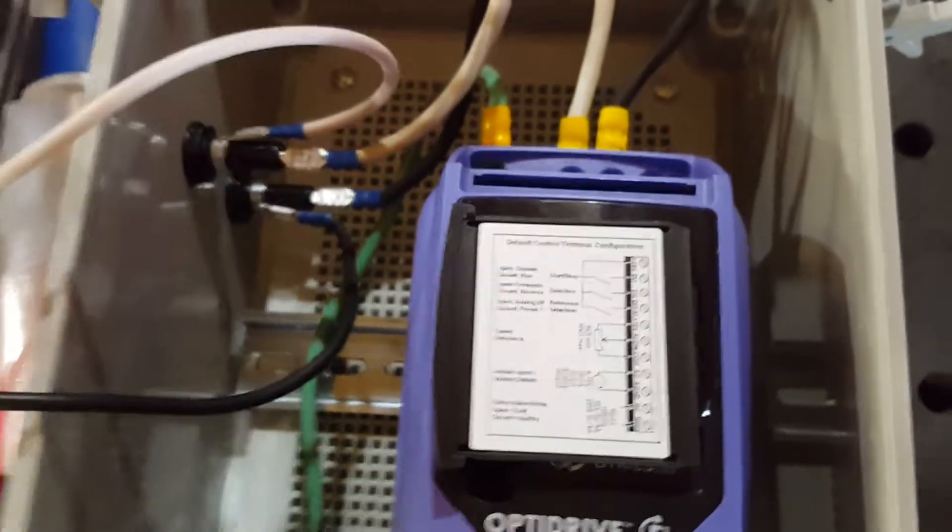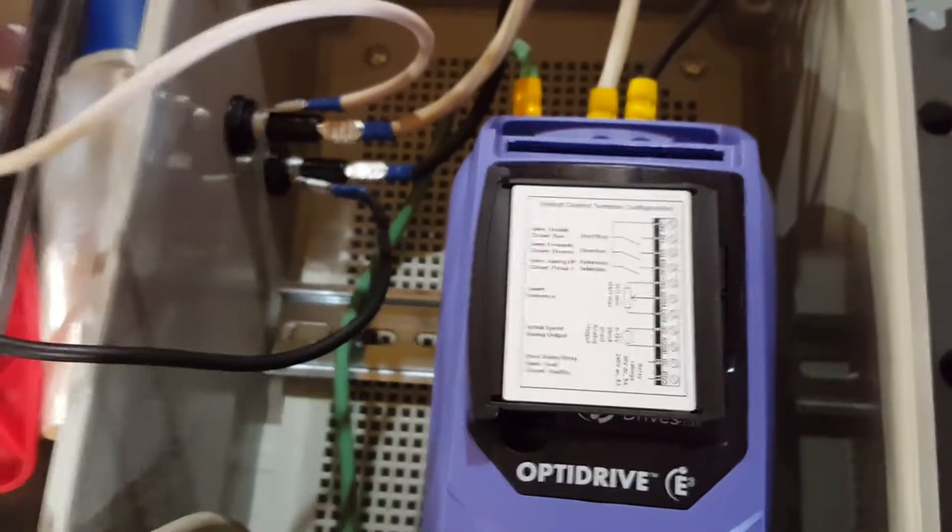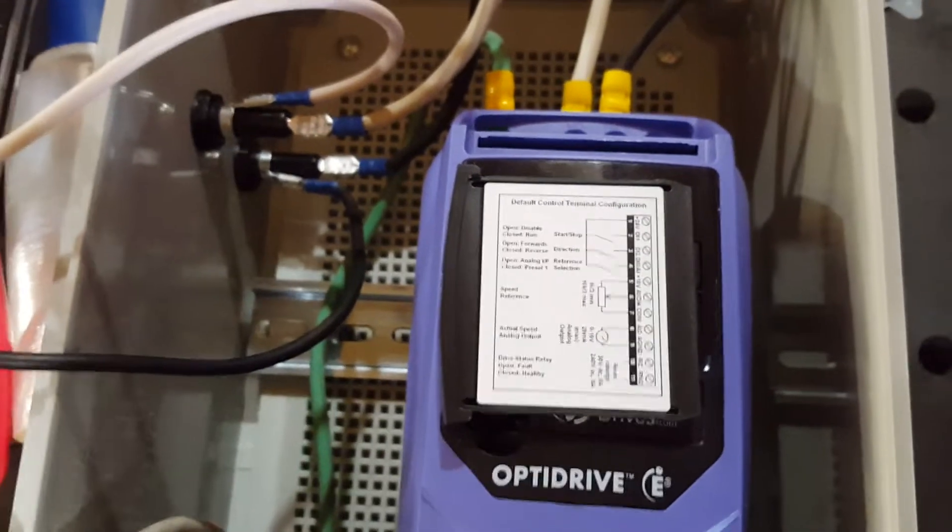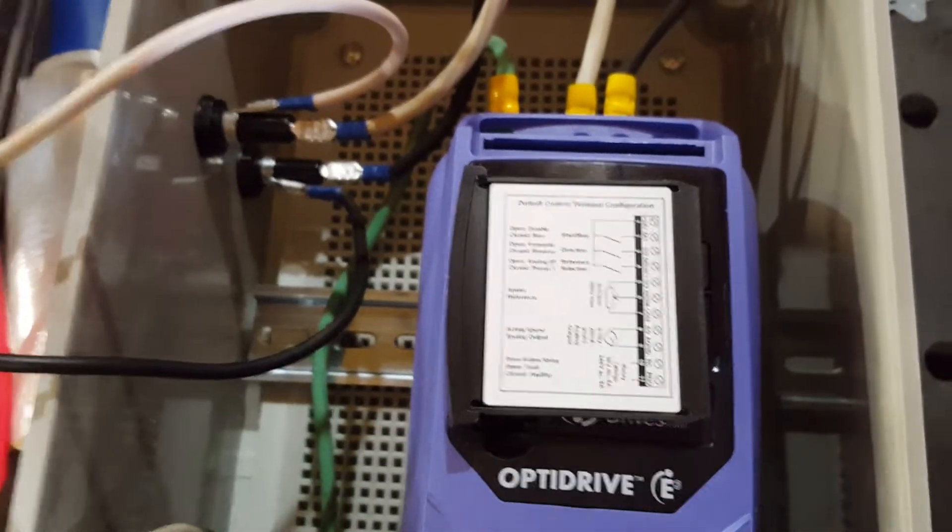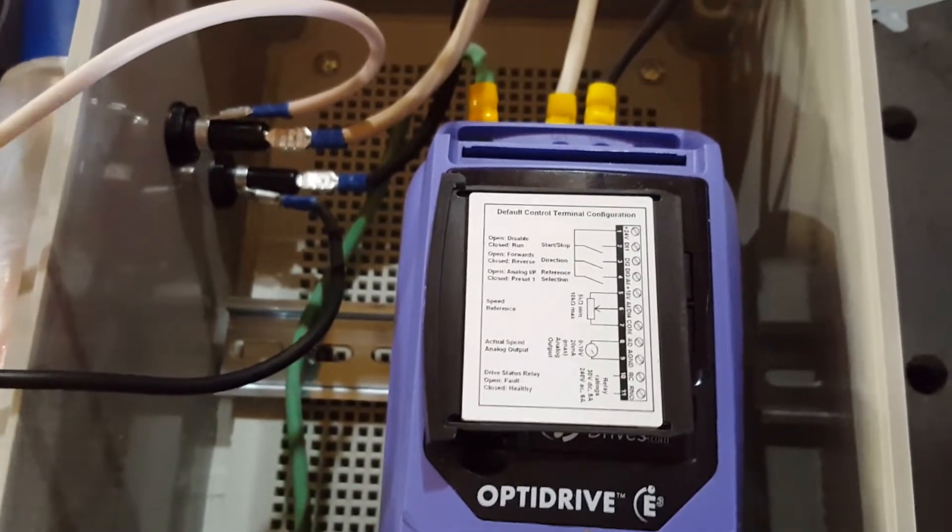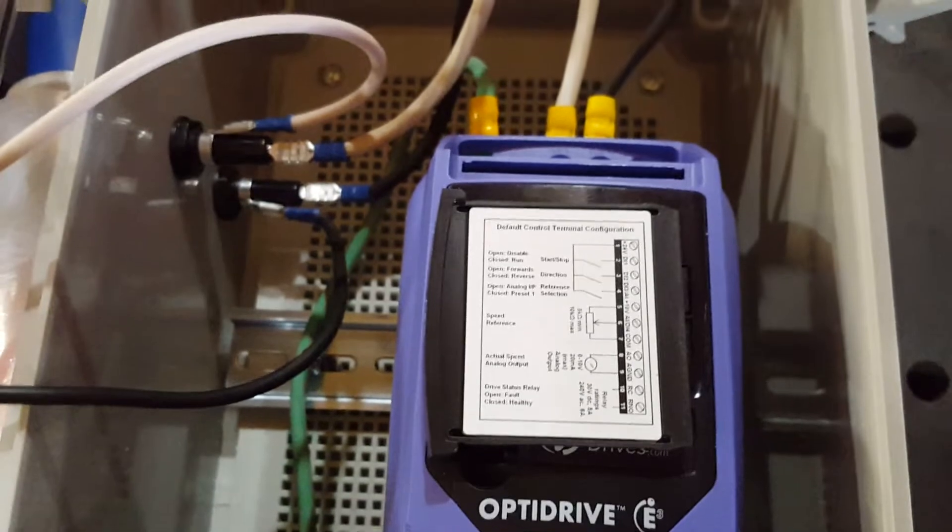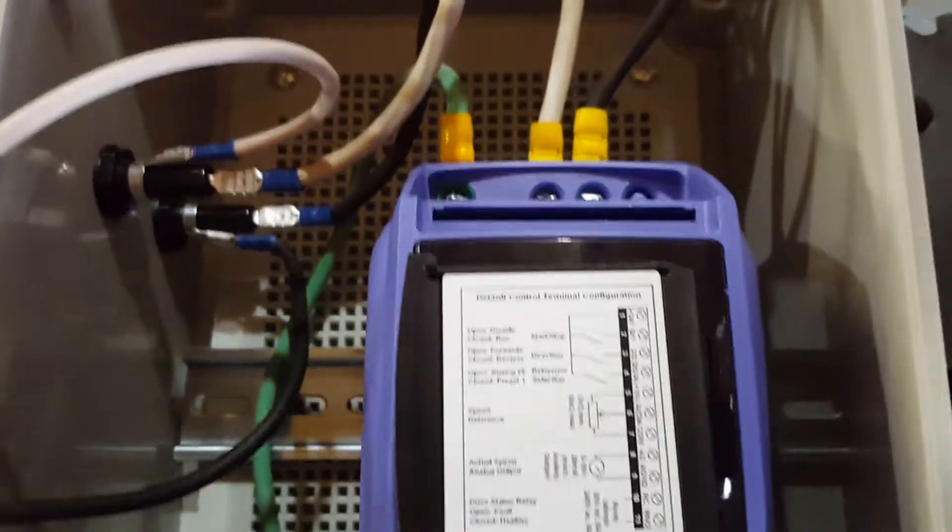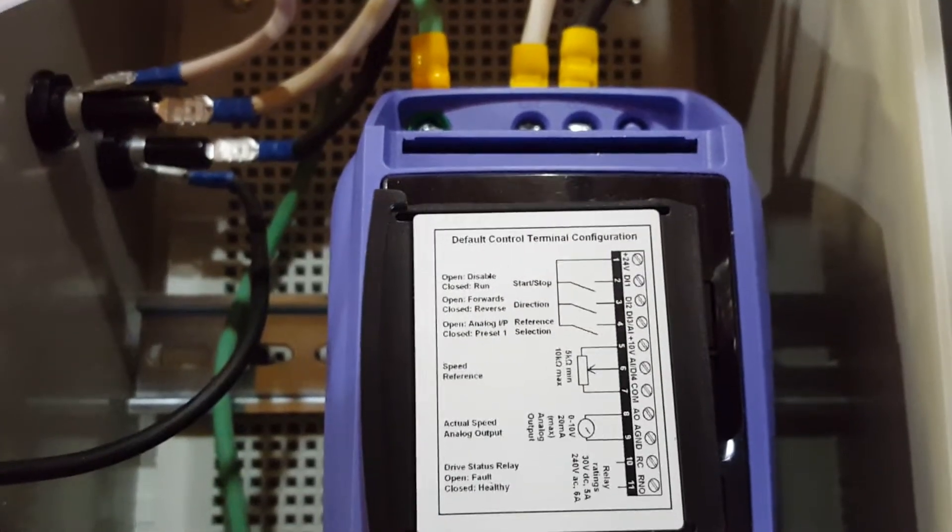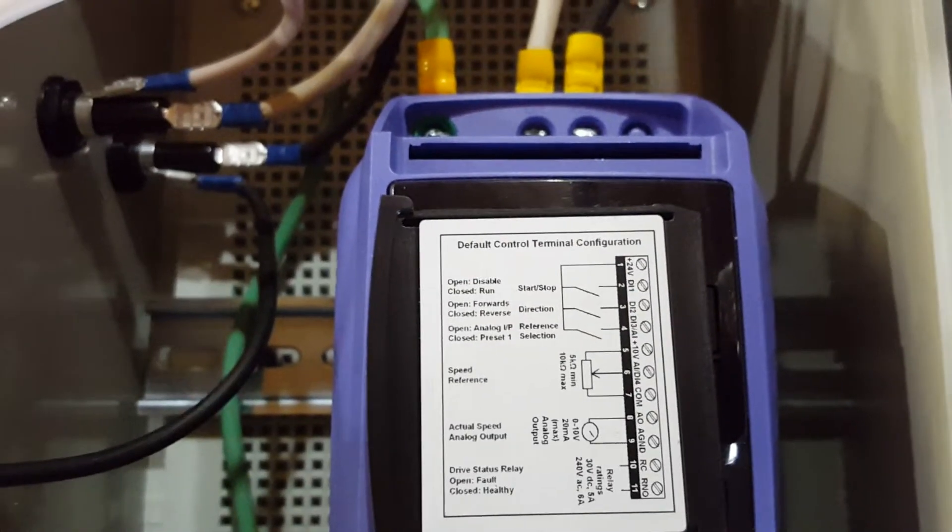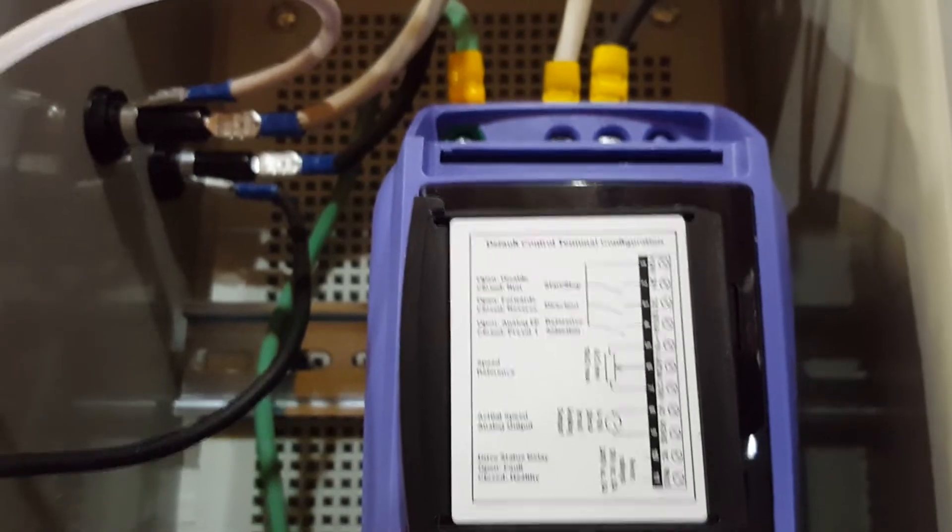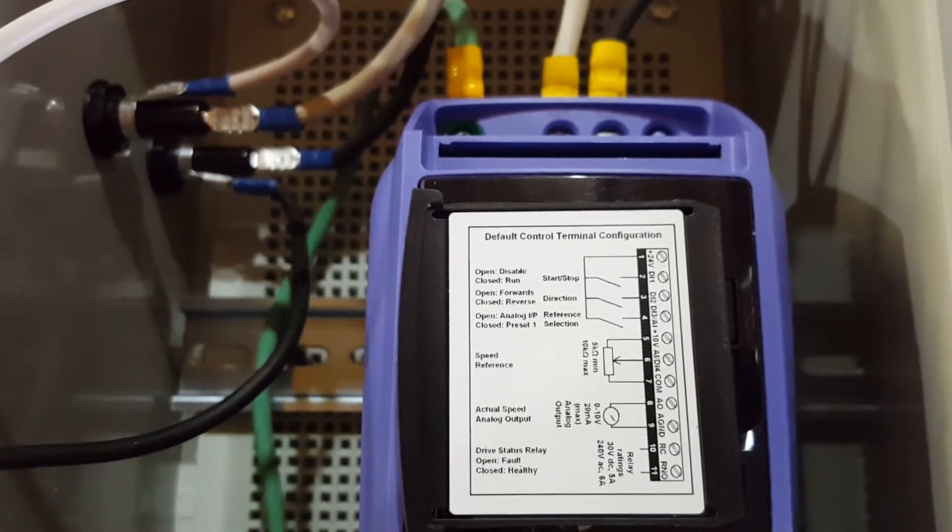And it will go to a predetermined speed based on the advanced settings of the drive. So if you want to push a button and automatically get 1,000 RPMs, you program that in the drive and then you add that button to four and you close all of those loops. Now that is more advanced, but yes, it's possible.